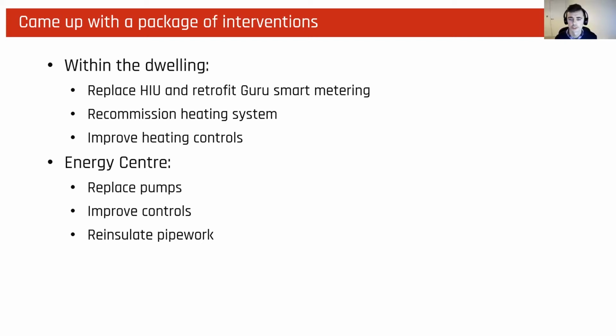Looking back at the plant room, there are a few aspects that we identified as room for improvement. So the pumps were oversized, and if we were to replace these, we could actually bring those energy costs down. And there was a similar case with the plant room controls and the current hydraulic arrangement. And again, talking about heat losses, the heat loss from pipework was higher than what we'd expect to see. So really, there was a re-insulation exercise there because we did identify areas of non-compliant installation.